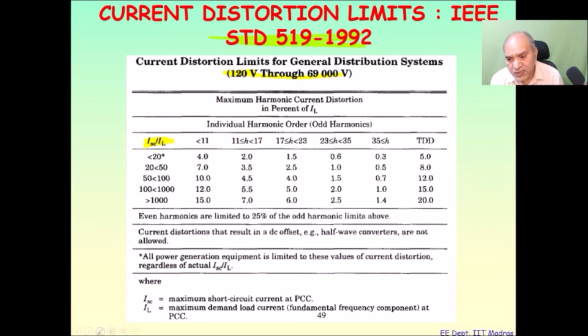And this shows basically the short circuit capacity of the bus. The higher the value of this parameter, or short circuit ratio you can say, SCR, the more sturdy the bus is. So this is less than 20, then 20 to 50, then 50 to 100, and then 100 to 1000 and so on. As we increase the short circuit ratio of the bus, it has more tolerance for the harmonics. So allowable TDD is 5, 8, 12, 15, 20. So a higher capacity bus can withstand more harmonics. This is the interpretation of this.